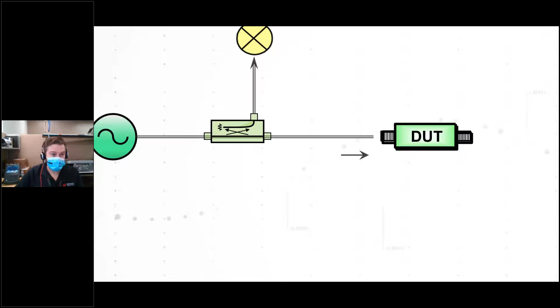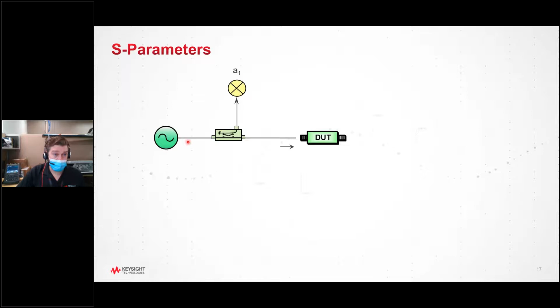So we do that with a coupler. And if you can see in this, the notation of the coupler, the arrow signals coming from this direction, and the arrow directs the energy to the receiver. And the energy coming in the reverse direction is sent to a termination. So in this case, it'd be a 50 ohm termination because we're working in a 50 ohm system. So the only signals being propagated into the device under test, and a small portion of that signal is being picked off and sent to this receiver we're calling A1, which is great. So now we know what's going in, and we can characterize that.